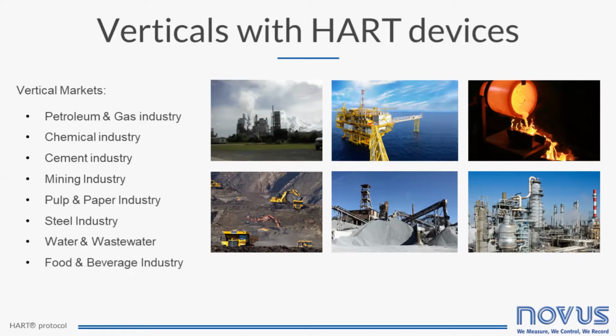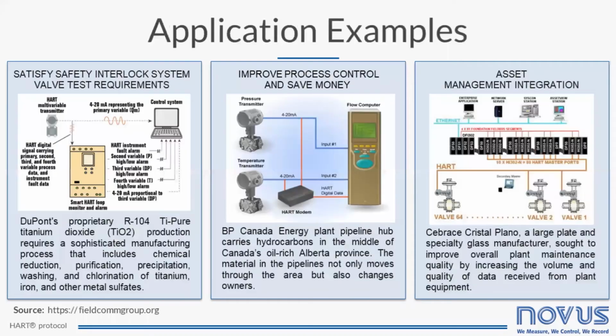DuPont, a chemical industry company, needed a better way to test safety interlock control valves during plant operations. Intermediate instrumentation was added to extract relevant data from the plant's HART instruments. Partial valve stroke testing of emergency shutdown valves was used during normal operations for fewer and shorter shutdowns. Over 100 control valves equipped with HART loop monitors were installed. So, valve safety interlock testing became a less labor-intensive and cumbersome operation.